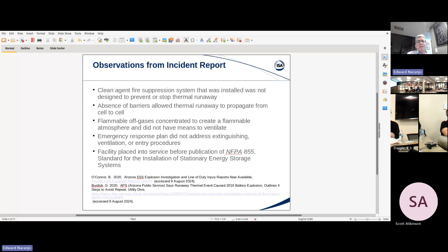That was another observation of the incident. Other factors also had an important effect: there was no emergency response plan. But perhaps the most important one is that back in 2019, five years ago, the National Fire Protection Association Standard 855 did not exist. This is now the prevailing standard for installing stationary energy storage systems, and many safeguards that could have prevented this incident were not in place back then.